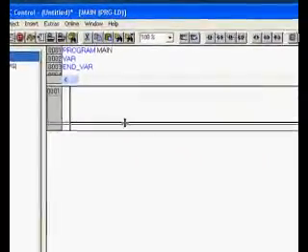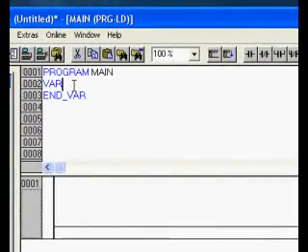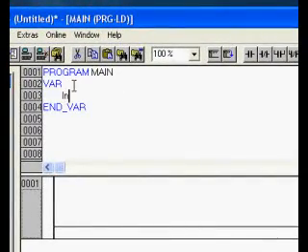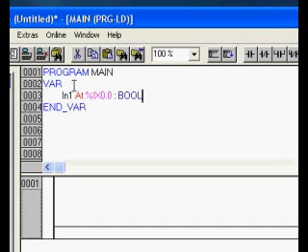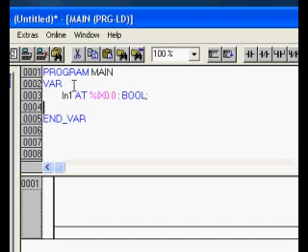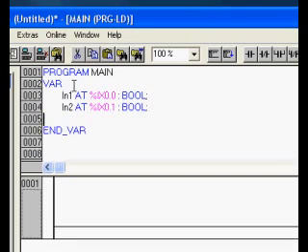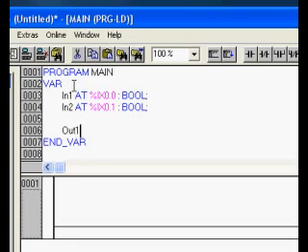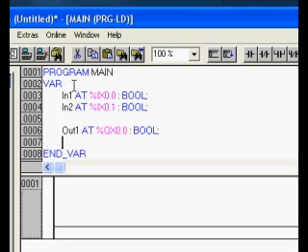Okay, so now the very first step I'm going to create some variables. TwinCat is tag based so I'm doing this manually, you can do a table if you want. What I'm typing, I'm creating variables and declaring an address. Now these addresses are just addresses I've made up to use and you need to do that whenever you're going to link physical IO. In order to run TwinCat you have to have what's considered a sync master which is at least one physical IO. So that's why I'm just going to declare two inputs and two outputs.